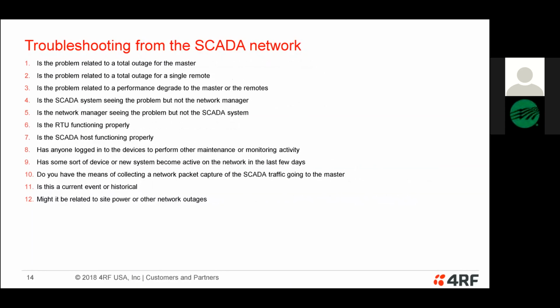The last one, number 12, came up with a utility in Louisiana on Friday, where they told me they were having a problem in the middle of the day. When I looked at the performance logs, I noticed the building temperature had gotten up to like 130 degrees during the daytime, even though it was supposed to be air conditioned. Apparently, after the ice storm, somebody went out there and turned the heater on continuously and left it that way. When the warm weather came back, the building turned into a kiln. It wasn't killing the radio, it was killing the power supply the radio was attached to. I could see the temperature go up and then see the DC voltage begin to experience a problem coming into the radio, because we monitor that too.